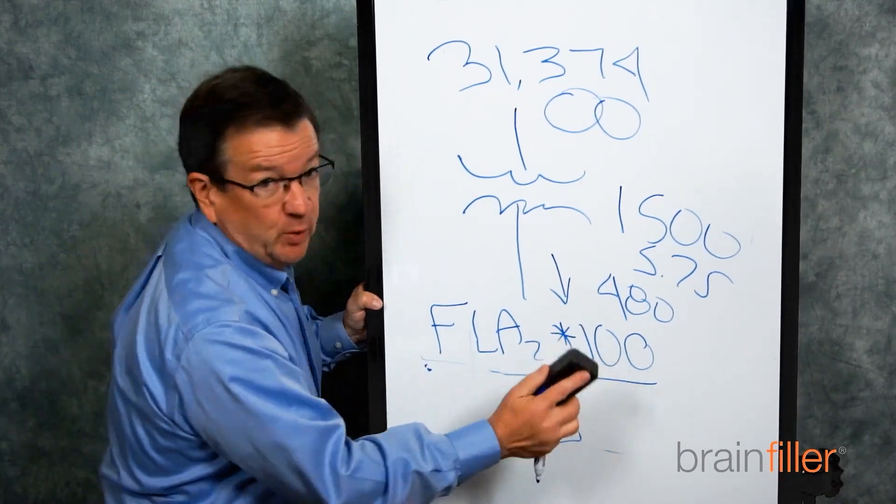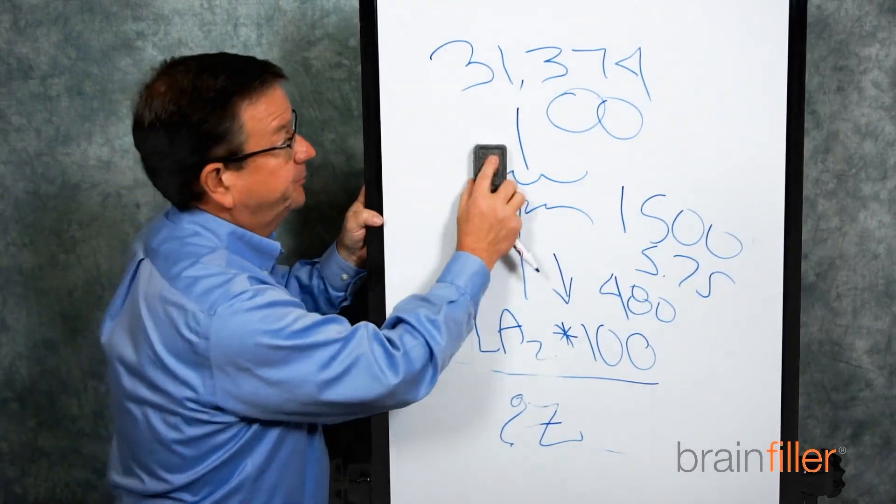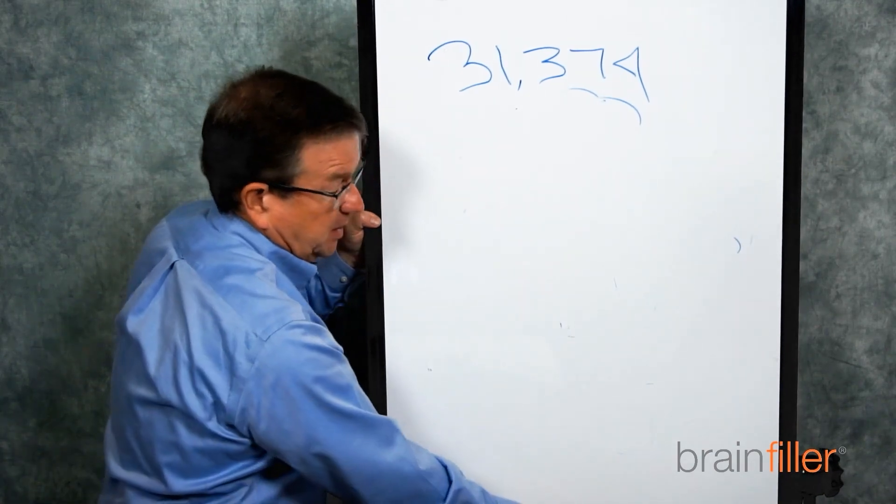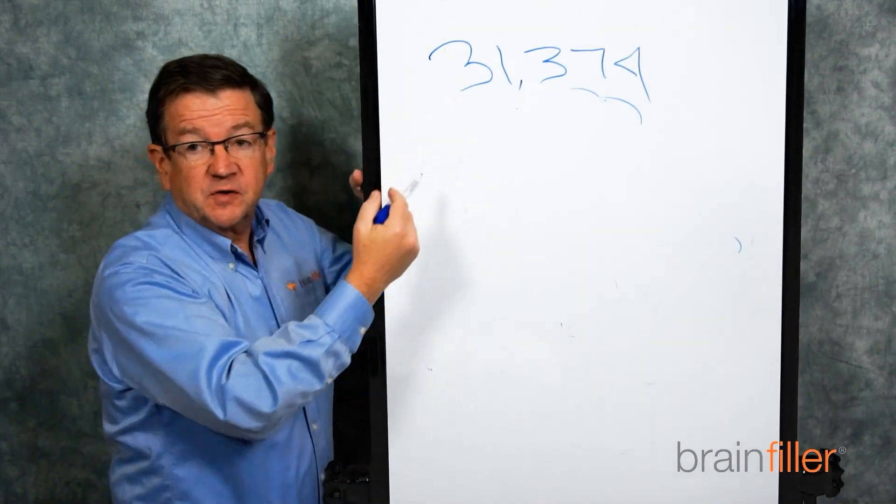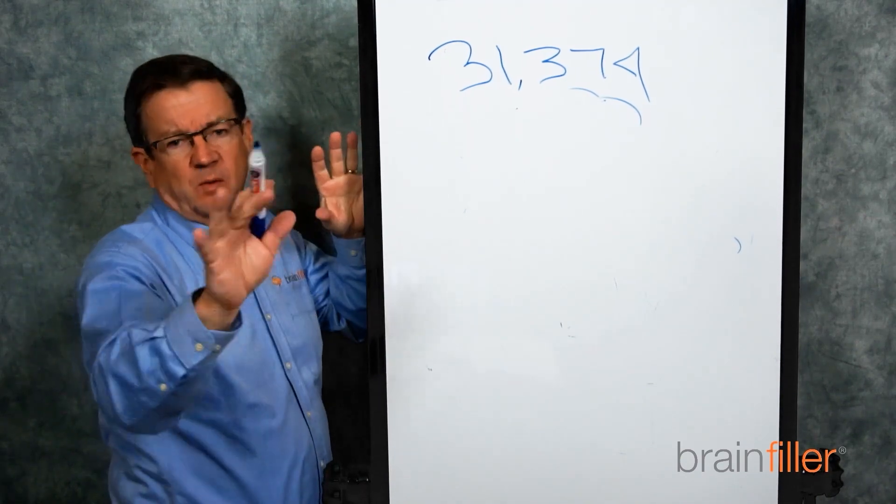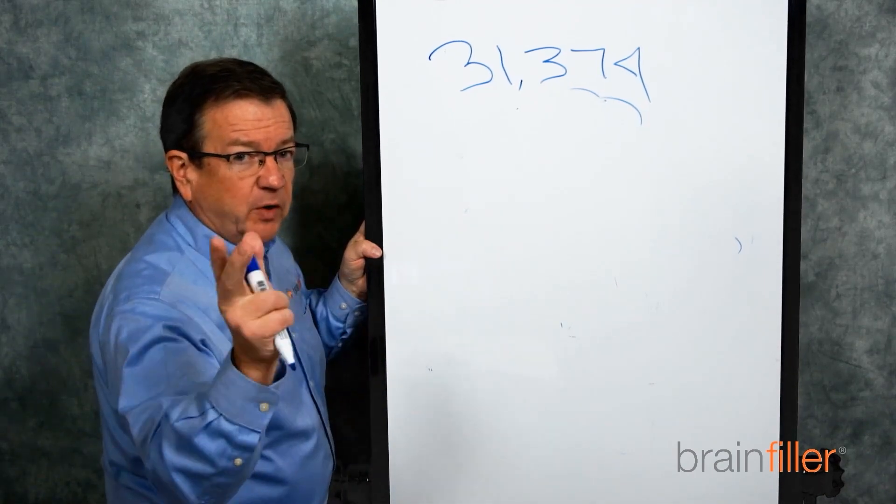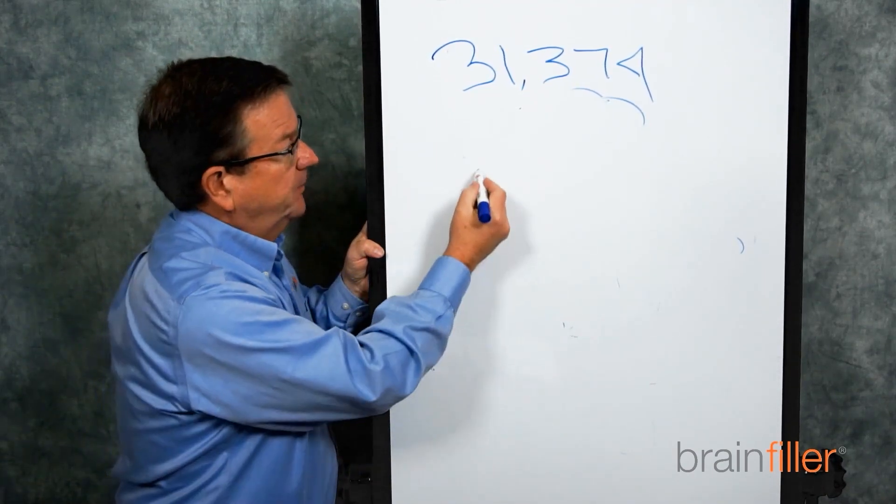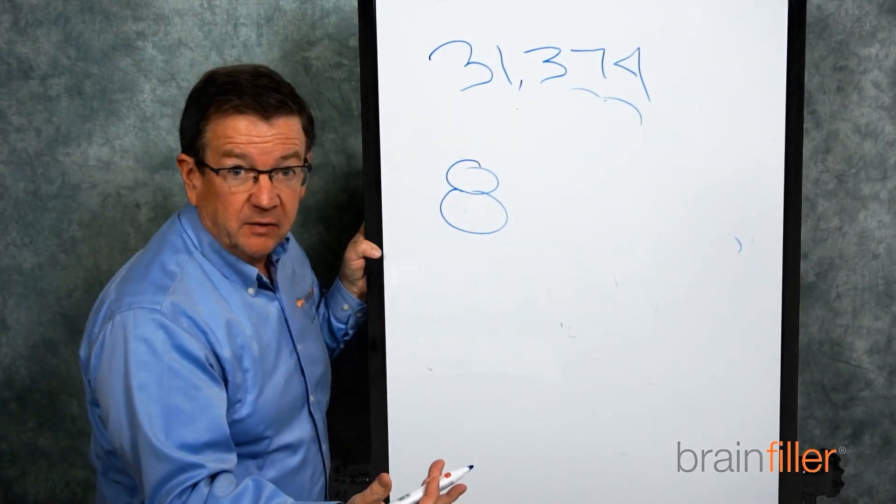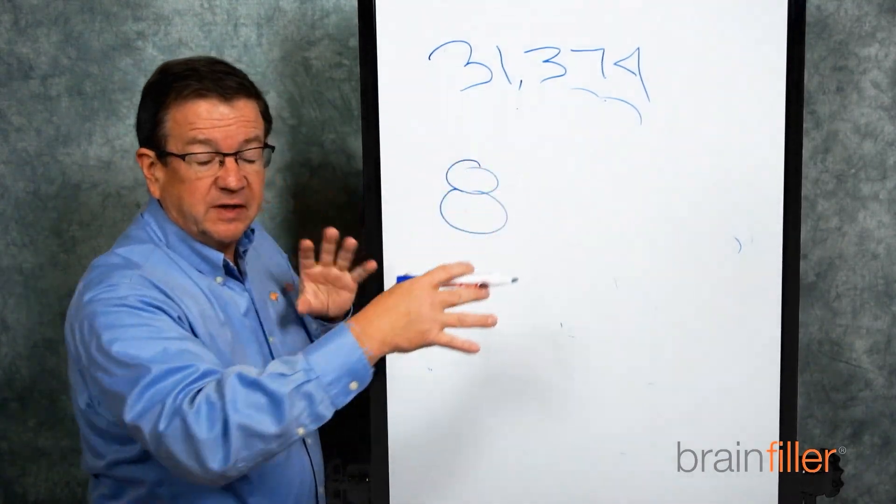So what you do with this, as far as an arc flash study, if that's all you have to go on, the next step is begin your study with the infinite source, 31,374. Many people say, oh, you're not supposed to do that. I'll explain what that's all about in a moment. Run your study, and what you're doing, going back to what I talked about earlier, is look at what is the arc rating of the PPE that you're targeting. Let's say it's 8 calorie.